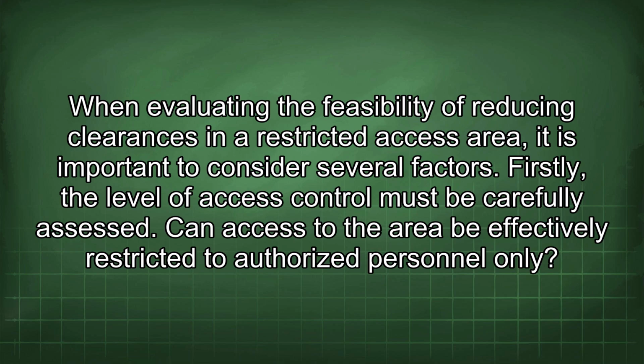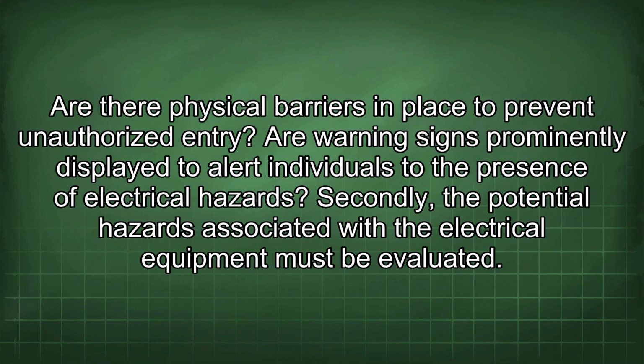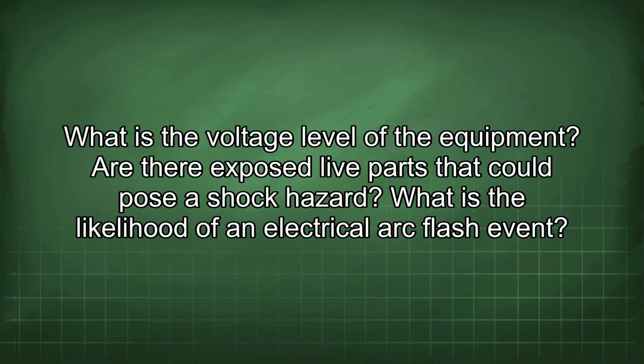Can access to the area be effectively restricted to authorized personnel only? Are there physical barriers in place to prevent unauthorized entry? Are warning signs prominently displayed to alert individuals to the presence of electrical hazards? Secondly, the potential hazards associated with the electrical equipment must be evaluated. What is the voltage level of the equipment? Are there exposed live parts that could pose a shock hazard? What is the likelihood of an electrical arc flash event?